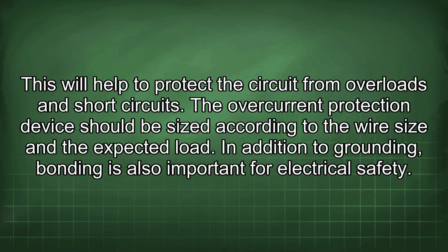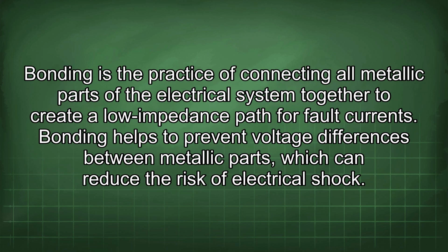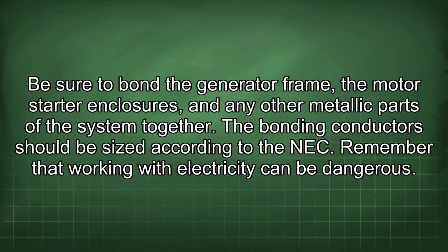In addition to grounding, bonding is also important for electrical safety. Bonding is the practice of connecting all metallic parts of the electrical system together to create a low impedance path for fault currents. Bonding helps to prevent voltage differences between metallic parts, which can reduce the risk of electrical shock. Be sure to bond the generator frame, the motor starter enclosures, and any other metallic parts of the system together. The bonding conductors should be sized according to the NEC.